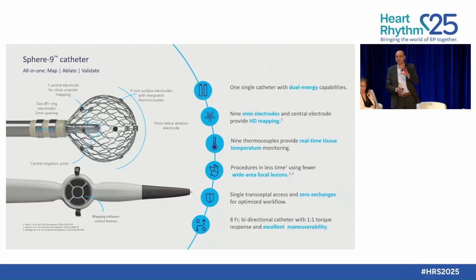The ablation is usually not delivered from each of the 9 electrodes. Ablation is delivered from the whole sphere as a single unit. So the electrodes that you see there are for recording temperature and electrogram, not for ablation, those mini electrodes. It is an 8 French catheter, so it goes through your standard sheath or any other 8.5 French sheath.